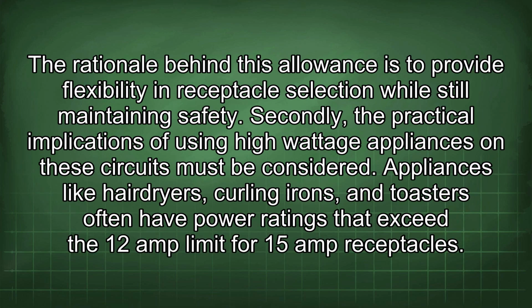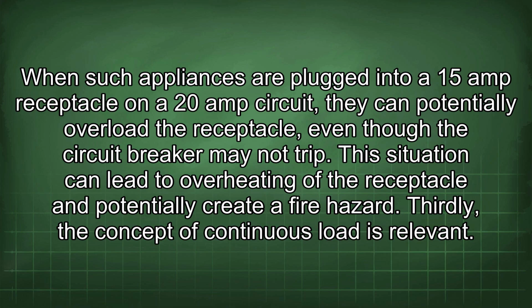The rationale behind this allowance is to provide flexibility in receptacle selection while still maintaining safety. Secondly, the practical implications of using high wattage appliances on these circuits must be considered. Appliances like hairdryers, curling irons, and toasters often have power ratings that exceed the 12 amp limit for 15 amp receptacles. When such appliances are plugged into a 15 amp receptacle on a 20 amp circuit, they can potentially overload the receptacle, even though the circuit breaker may not trip. This situation can lead to overheating of the receptacle and potentially create a fire hazard.